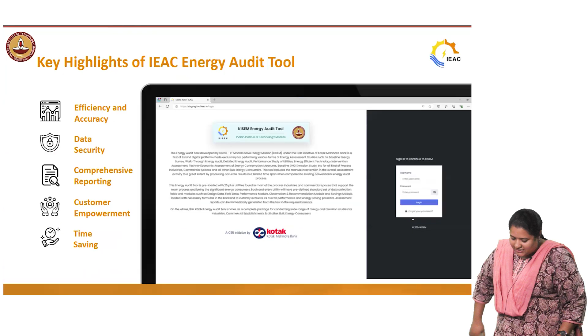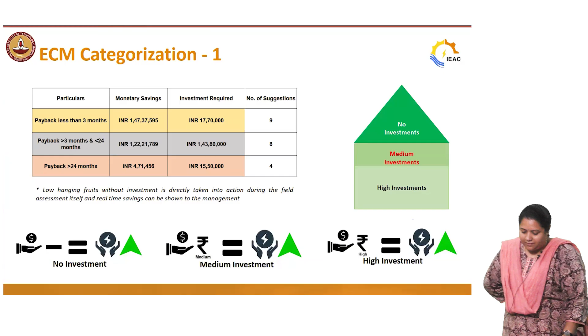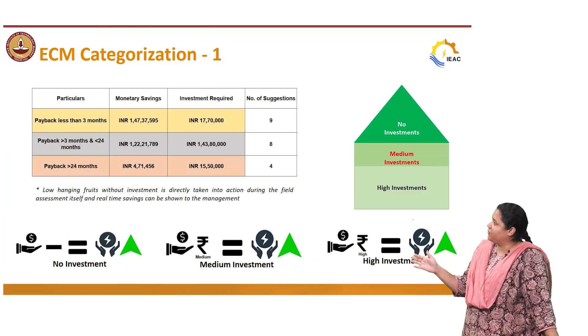The energy conservation measures are categorized into two types predominantly, one based on payback and monetary savings. There are three variants: a very low-hanging investment that can be implemented with almost zero cost—for example, leakages that can be sealed with a sealant, which is very small compared to the ROI or efficiency gained. Then there are ones with a payback of less than 3 months, a mid-range of 3 months to 2 years, and ones above 2 years. That's one type of ECM categorization we do.